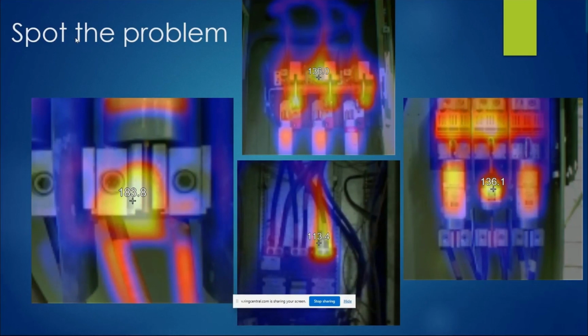It's showing an imbalance where one leg is pulling a much higher current than the rest, and it could also be a termination issue, given the fact that the heat is located right near the termination block. The upper one is showing what we call the stabs, also known as knives. The knives or stabs are where the three actually engage in the top of the disconnect switch. They're building a high heat signature. This is something we can identify easily with the infrared scan.